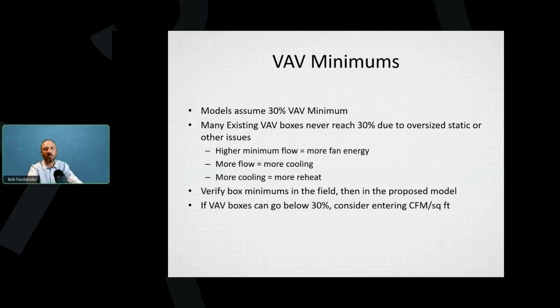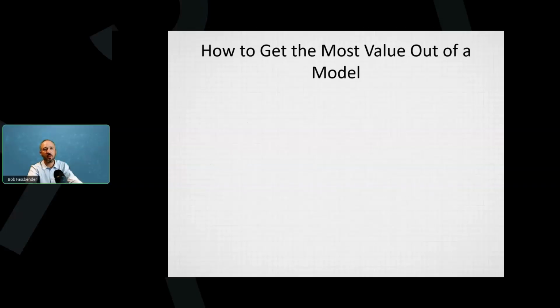Just one thing in terms of the model, sometimes you can change it to CFM per square foot, because many VAV boxes can go below 30%. And so that's just one input, if you're familiar with modeling, that you can enter.